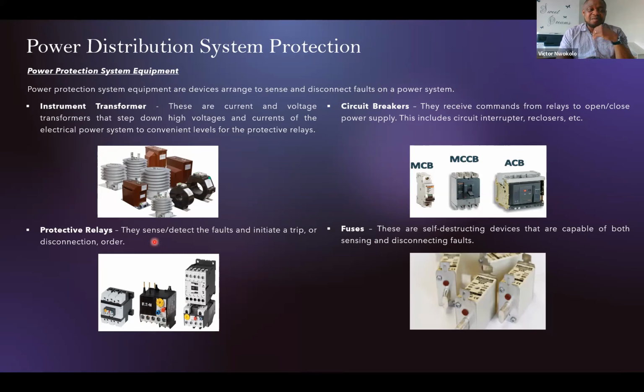The protection relays monitor the current flowing through the system and the voltage within the system against a predefined setting. And if the current being read is abnormal, like the current exceeding the predefined setting, the protection relay sends a trip signal to a circuit breaker to say trip, because it has picked up a fault. But a fuse can also sense and trip at the same time.